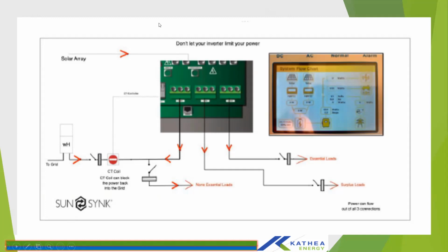And then from your CT meter, the same line, you then supply your non-critical loads. That is high power loads, stoves, geysers, and so forth, and high inductive loads. Preferably, you connect them as non-essential loads, right? And then the same line goes to the grid point on the inverter. So the system uses this point as an input-output port. When the system runs short of battery and PV to supply the non-essential loads, it will simply use this port as input and then supply your essential loads connected on the load output.